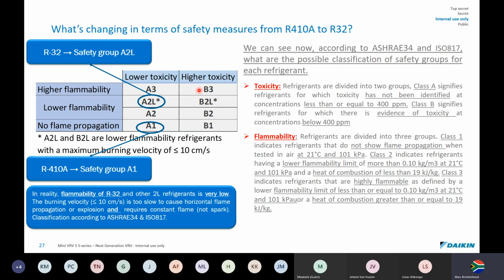We can see here that R32 falls into a lower toxicity group as well as low flammability, and R410A also falls in this group of an A with a 1 because it's not very flammable at all. R32 is slightly flammable, so it gets the number 2 on it.